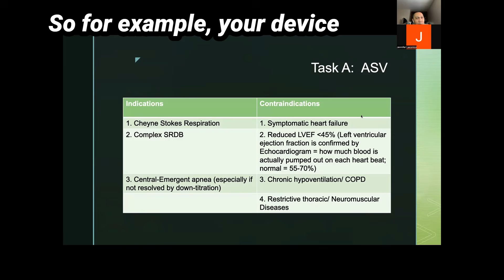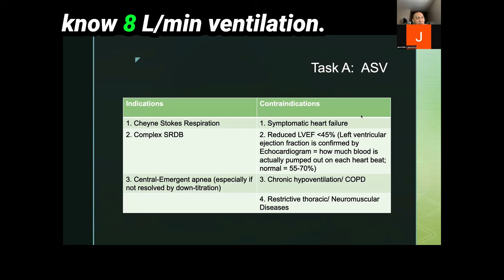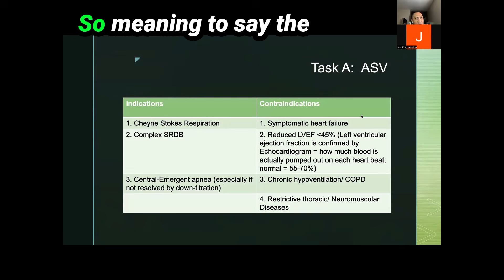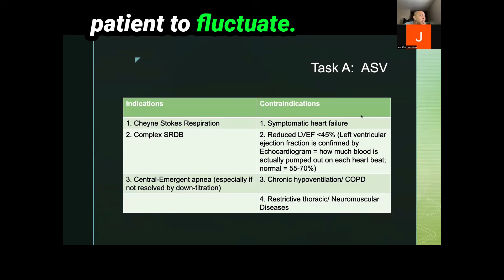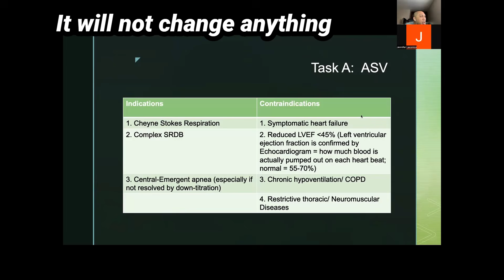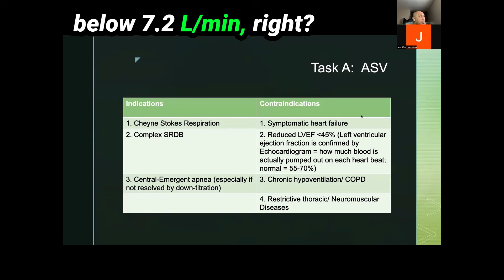So, for example, your device monitored your patient. The patient has a minute ventilation of 8 liters, right? So then the device will know 8 liters per minute ventilation. The 90% of that is what? 7.2 liters, around that. So meaning to say, the device will allow the patient to fluctuate, even if it drops to 7.5 or 7.3, it's okay. It will not change anything until the patient drops below 7.2, right? That's how it looks at it.